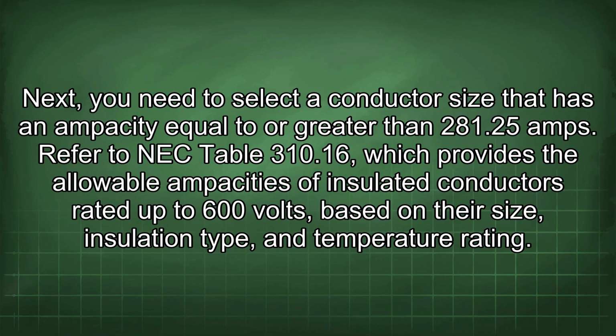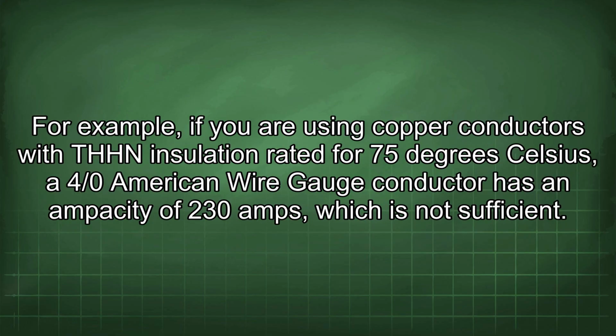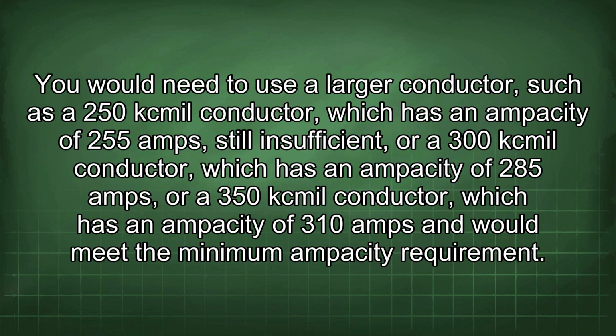Next, you need to select a conductor size that has an ampacity equal to or greater than 281.25 amps. Refer to NEC Table 310.16, which provides the allowable ampacities of insulated conductors rated up to 600 volts, based on their size, insulation type, and temperature rating. For example, if you are using copper conductors with THHN insulation rated for 75 degrees Celsius, a 4/0 AWG conductor has an ampacity of 230 amps, which is not sufficient. You would need to use a larger conductor, such as a 250 kcmil conductor, which has an ampacity of 255 amps, still insufficient, or a 300 kcmil conductor, which has an ampacity of 285 amps, or a 350 kcmil conductor, which has an ampacity of 310 amps and would meet the minimum ampacity requirement.